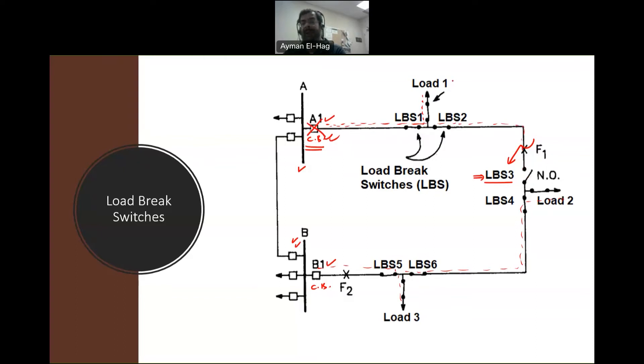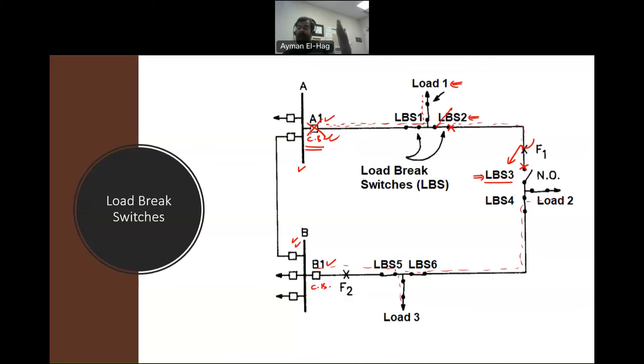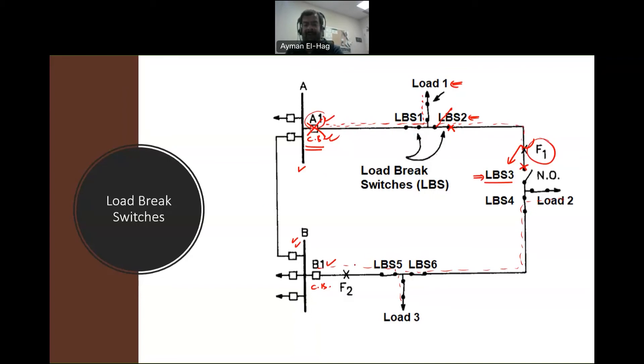Once A1 opens, the fault at F1 has no power from either side, so it stops. But now load 1 has no power. To restore power while isolating the fault, we open the normally closed LBS2, isolating the fault from both sides. Then we close circuit breaker A1 again. Since LBS1 is still closed, load 1 gets power restored. The fault section remains de-energized so we can clear it. After repair, we close LBS2 again.